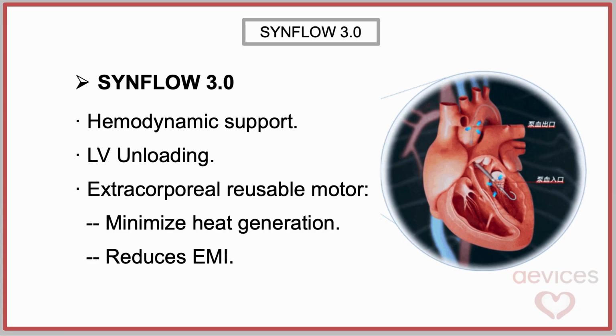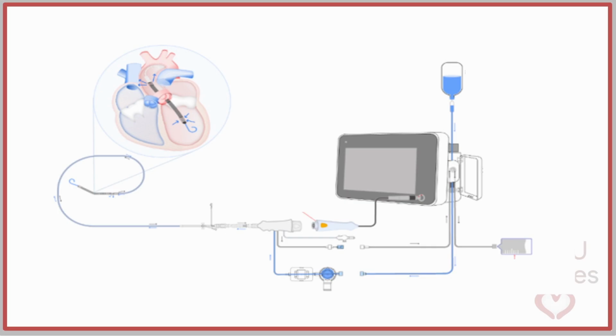The system unloads the left ventricle by continuously pumping blood from the left ventricle into the ascending aorta through a transvalvular axial flow catheter. Unlike Impella CP, Synflow 3.0 features an extracorporeal reusable motor, while only the pumping catheter is inserted into the patient. This architecture aims to reduce device cost, simplify maintenance, and minimize heat generation inside the body. It also reduces electromagnetic interference, substantially reducing the likelihood of device cross-interference.